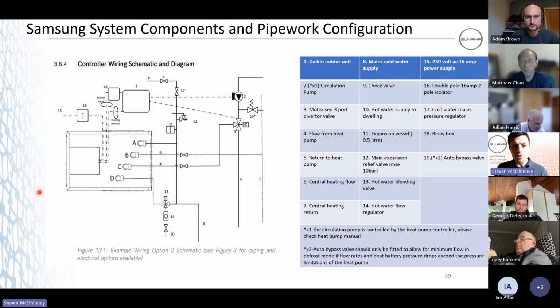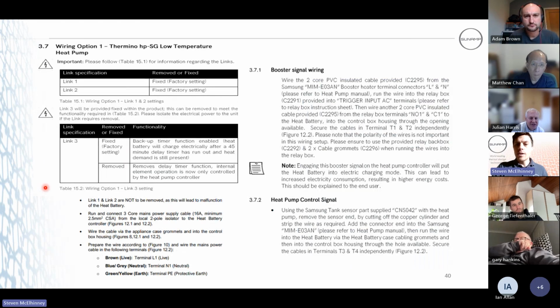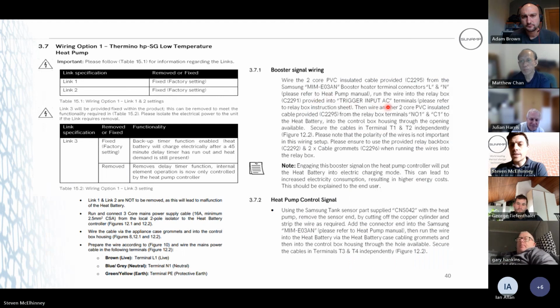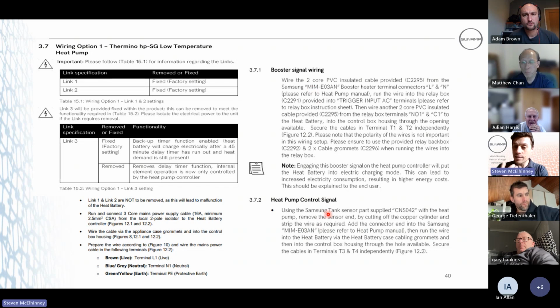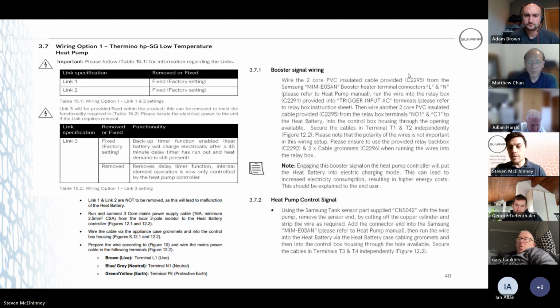I've not got any pictures for the Samsung, unfortunately, so I'll just have to talk you through this. Again, you've got your pipework schematic there, so it's fine. The booster signal wire is the same deal. From the heat battery, terminals 1 and 2 go into NO1 and C1 of the relay box, and from the trigger input AC terminals, you run another 2-core and wire that into the heater terminals L and N of the MIM. For the tank sensor side of things, you get the Samsung tank sensor supplied, cut the plug off the end, strip the wires, and plug it into T3 and T4, and then run that back to your MIM control circuit, and that's how you do the Samsung.